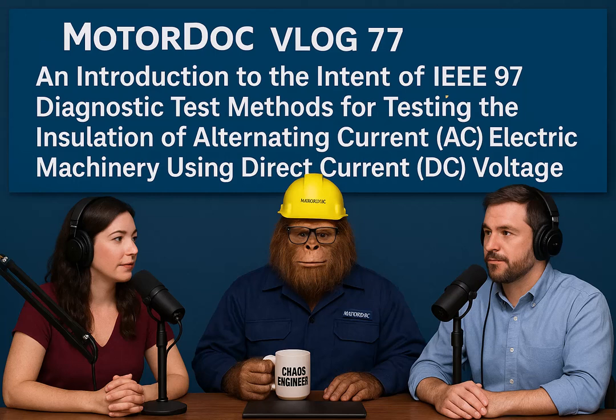Okay. And what determines how high you ramp the voltage? The end of test, or EOT, voltage? The guide bases the EOT on the machine's rated line-to-line voltage, the VLL. They use factors derived from standard tests, basically converting the AC rating to a DC equivalent, usually multiplying VLL by 1.7. Right. And then they apply an additional factor, typically around 85%, based on experience that these ramp tests are more sensitive and applied for longer than, say, a quick withstand test.